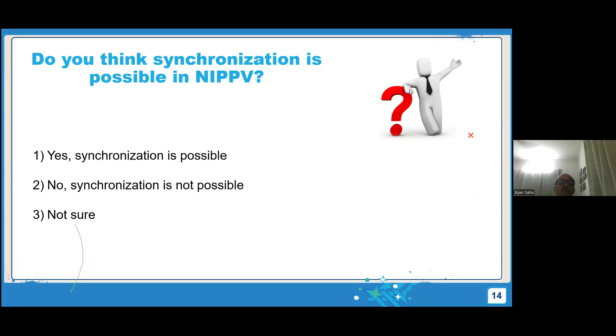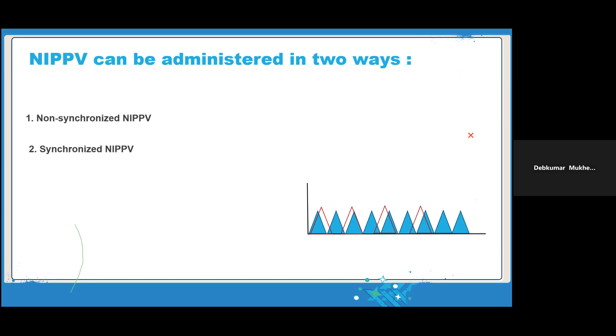Previous slide. So if synchronization is not possible, what happens? You see, these are the spontaneous breaths. Next, just click. So if you see, these are all ventilator breaths. If you see the first breath, when the baby was in the inspiratory phase, at that time expiration had started. In the second breath, when the baby was in expiration, there was an inspiration of the ventilator. In the third breath, when the baby was in the exhalation phase, the ventilator was in the inspiratory phase. In the last slide, next, next. So you see, just go to the previous slide.